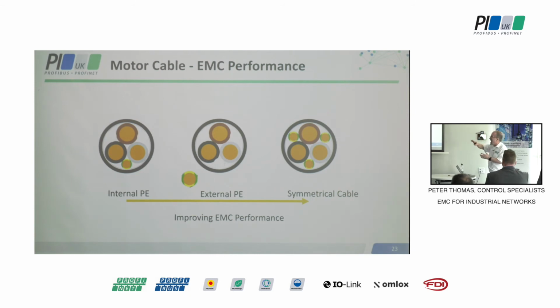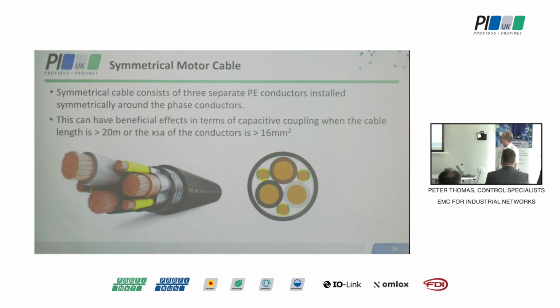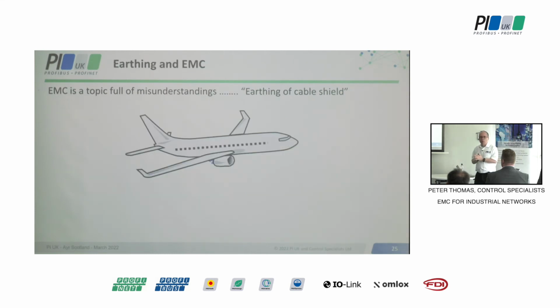But this is where industry is starting to move towards, but by definition, it's an expensive cable, so it's not particularly popular. This is what the cable looks like. I'm going to explain the benefits of that shortly. Okay, so the world of EMC, the strange world of EMC. The earthing, the grounding of shields. If you say earthing or grounding within earshot of an EMC consultant, he will shoot you, because it's an immediate indication that you don't fully understand what you're talking about.